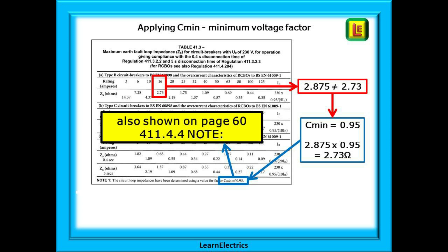Look immediately below the table at the notes. It tells us that there is a C min factor of 0.95 to take into account. This is shown below each of the tables and also shown on page 60 in regulation 411.4.4 under note. C min is the minimum voltage factor and this allows for voltage fluctuations in the supply.